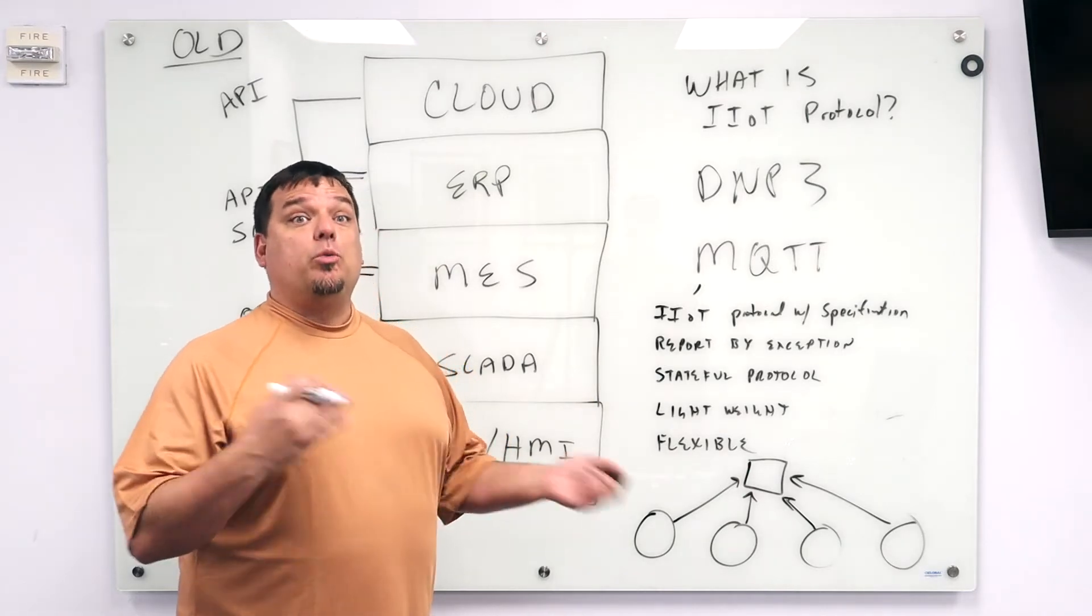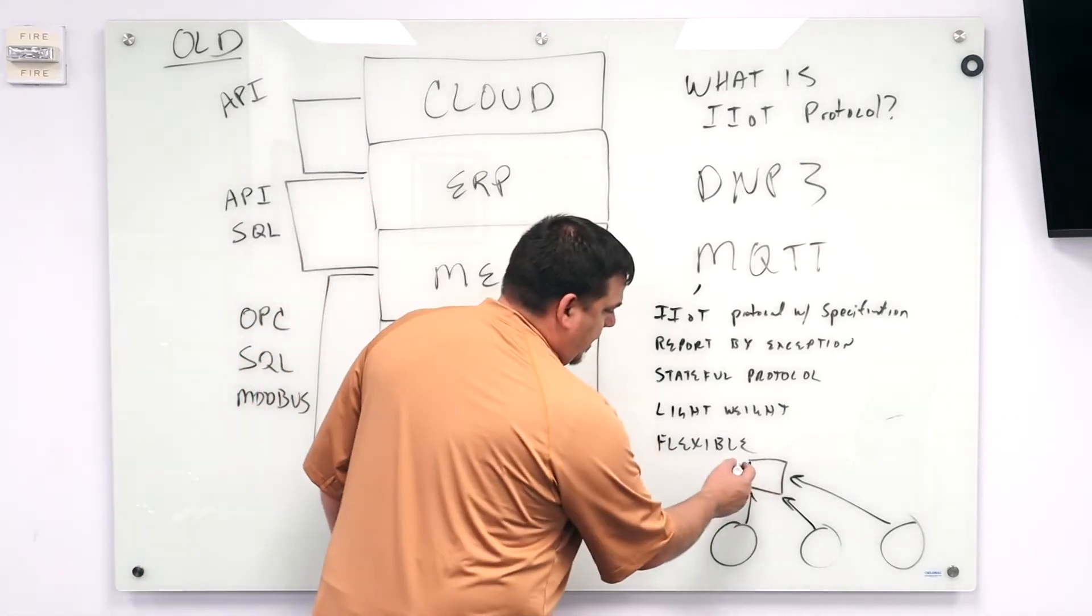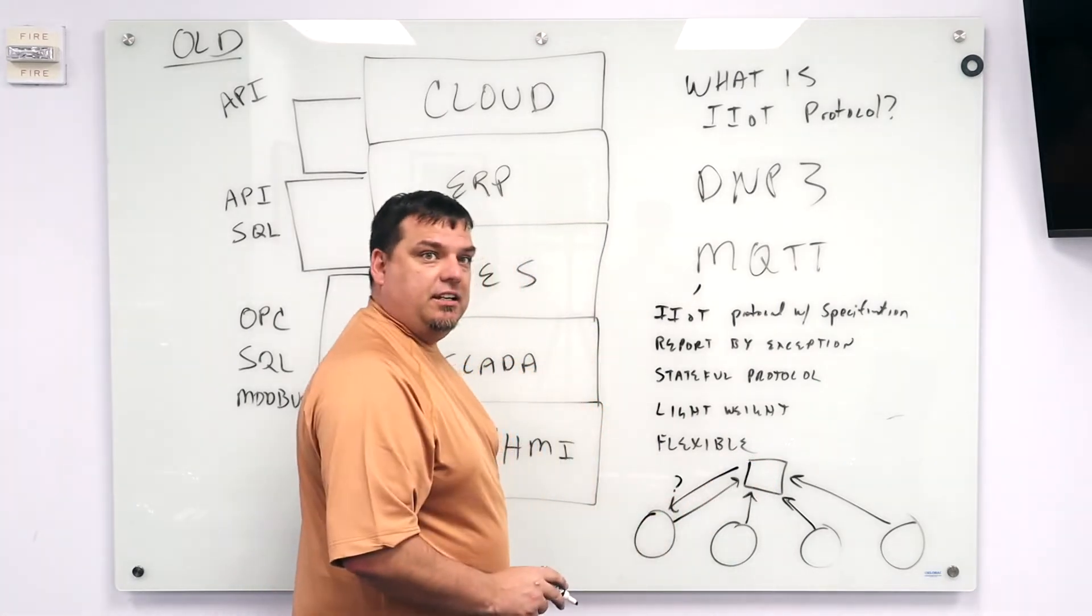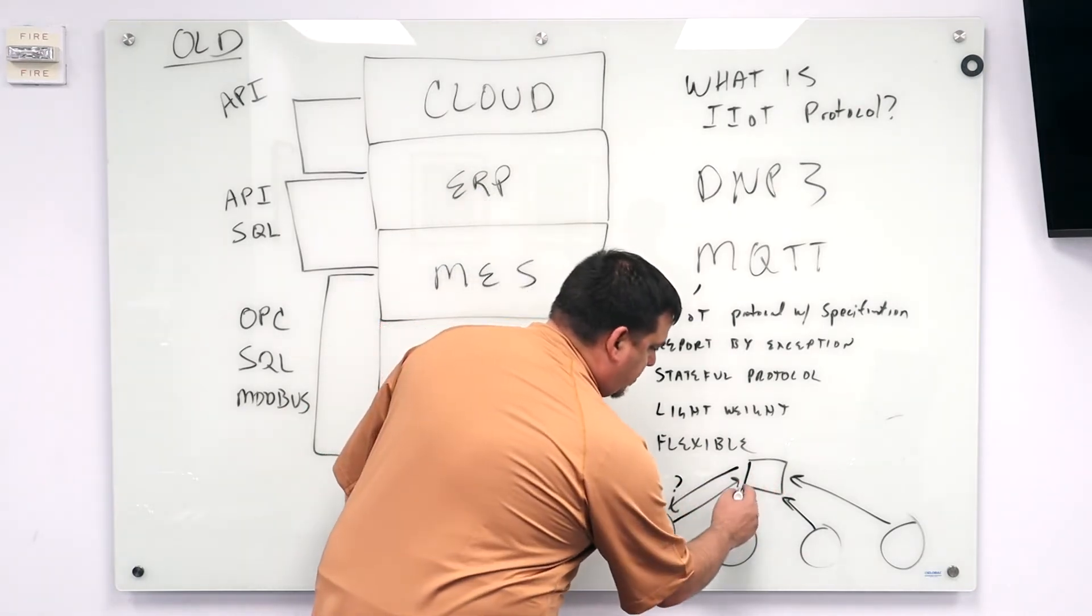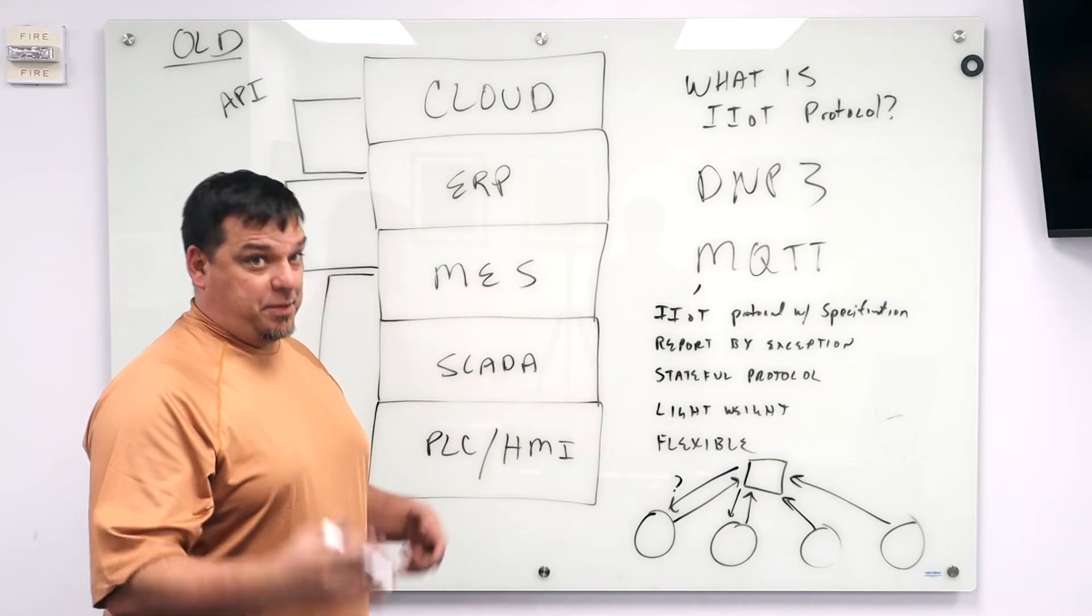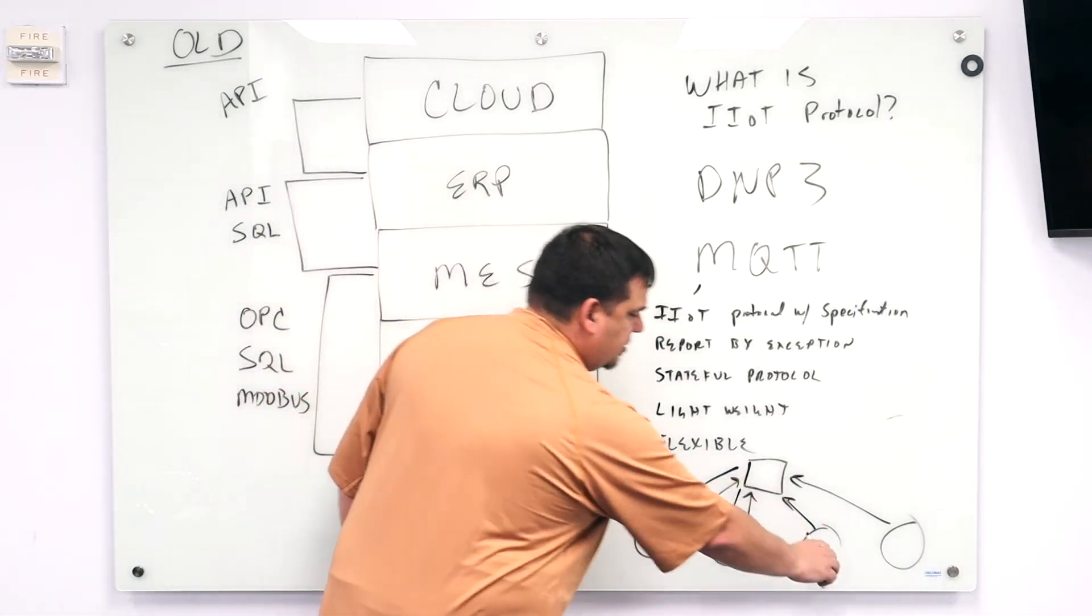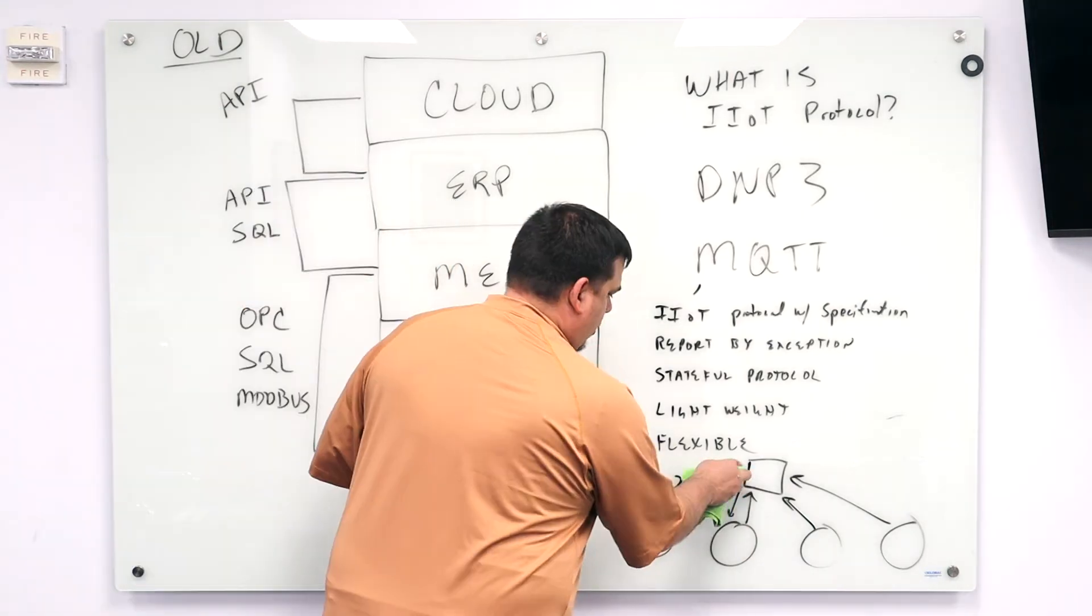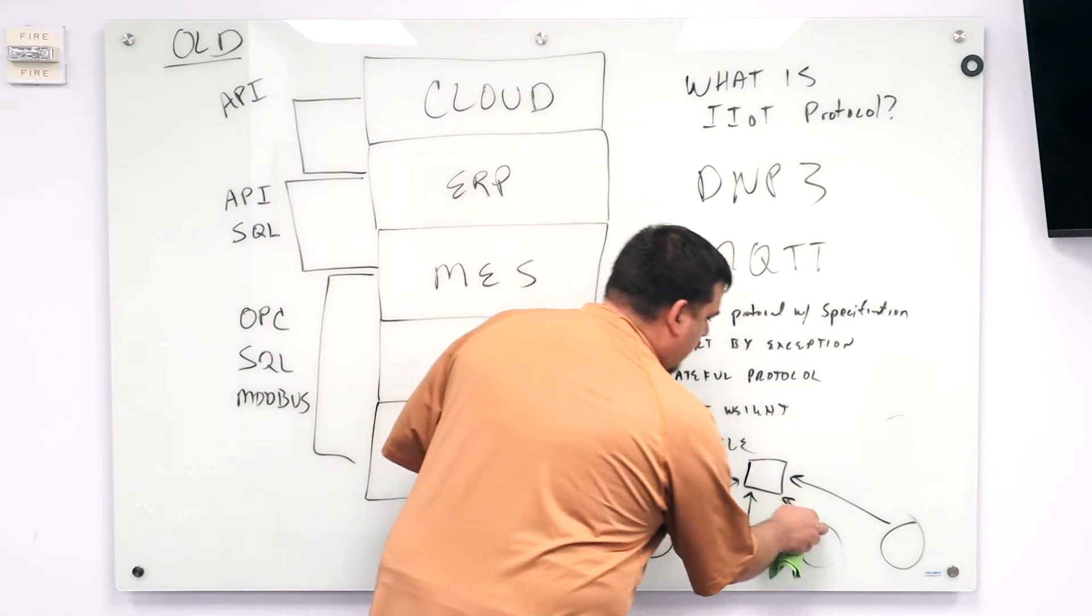The traditional way is a poll response method, right? OPC UA, which we'll see over here in a second. OPC UA, where my server makes a request to the PLC and the PLC responds to the server. Then it moves to the next request. The advantage of IIoT protocols, specifically MQTT, is that MQTT publishes the changes to the broker. Only the things that changed, report by exception. So obviously what you can see is bandwidth is much lower and it's much more efficient.